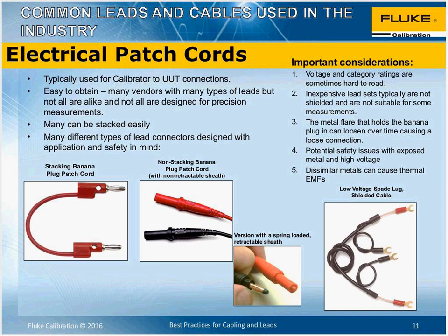The one shown there on the left has a non-retractable sheath, and basically you would stick that into the front of the calibrator. The reason for that sheath is to prevent, as you're retracting it out of the calibrator, say you had 1,000 volts on that wire, any chance of coming in contact with that. So it is definitely a safety feature. There's another type there that I show that is spring loaded, that allows you to retract that. And the reason for that type is sometimes the receptacle that you would plug those into may not be fitted for a sheath. Using this type, it allows you to plug it in, and the sheath retracts so that you can use it with that instrument.